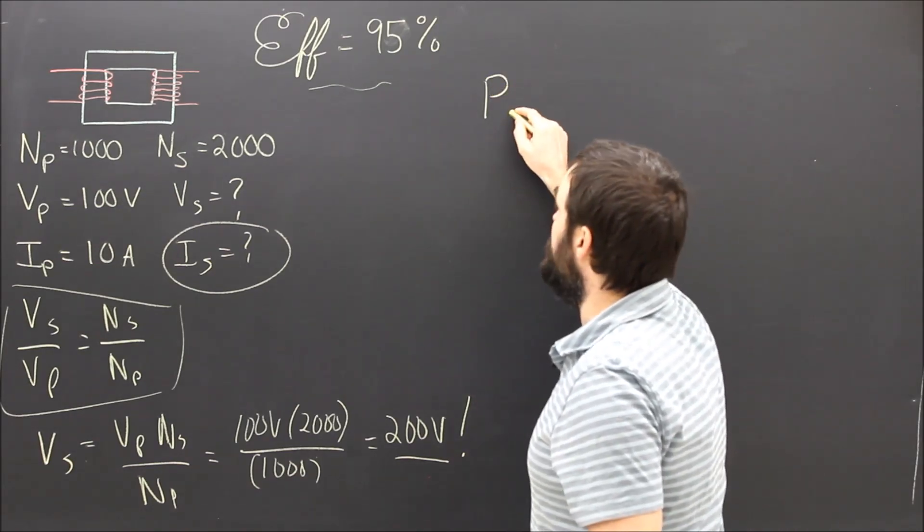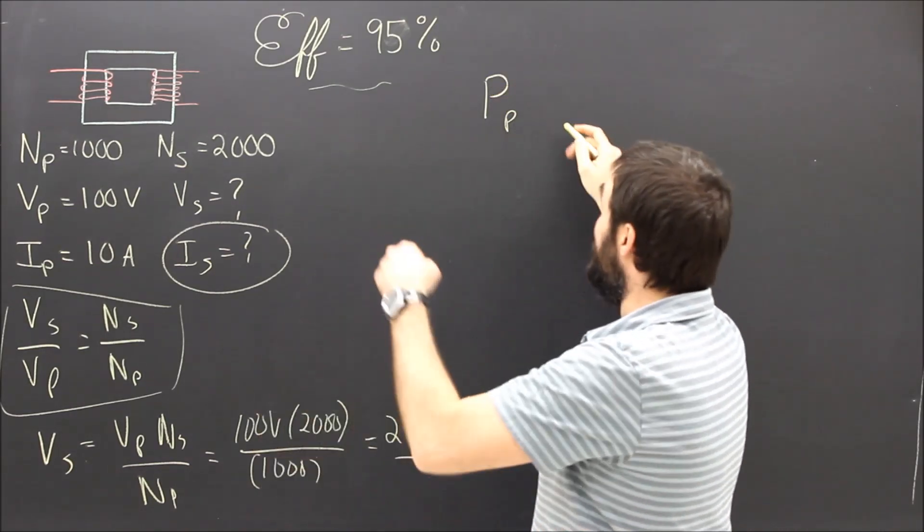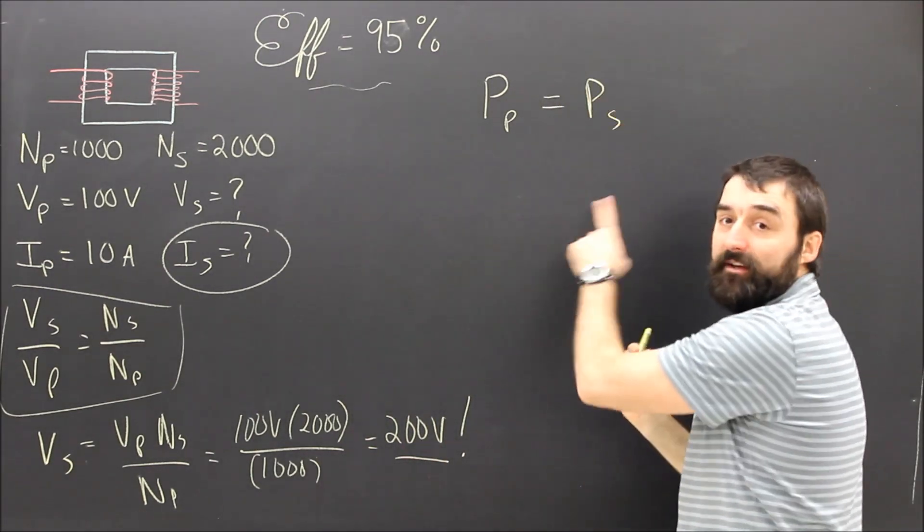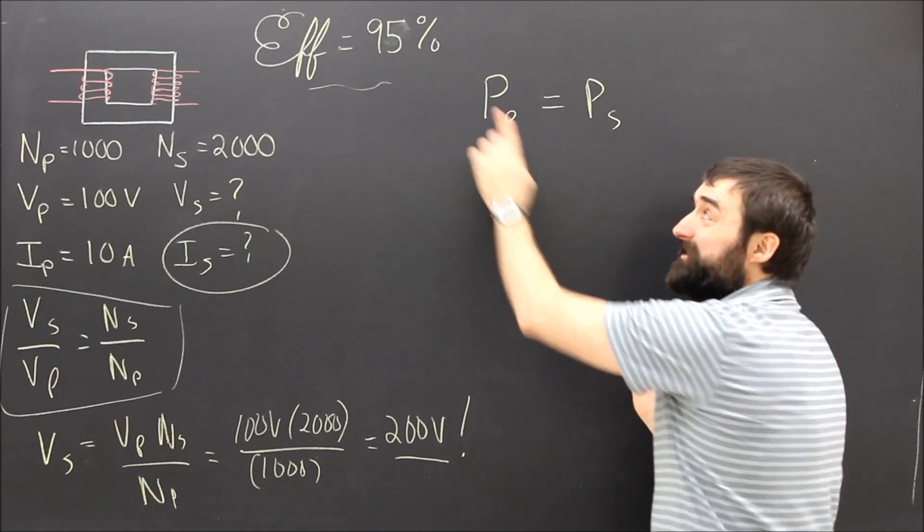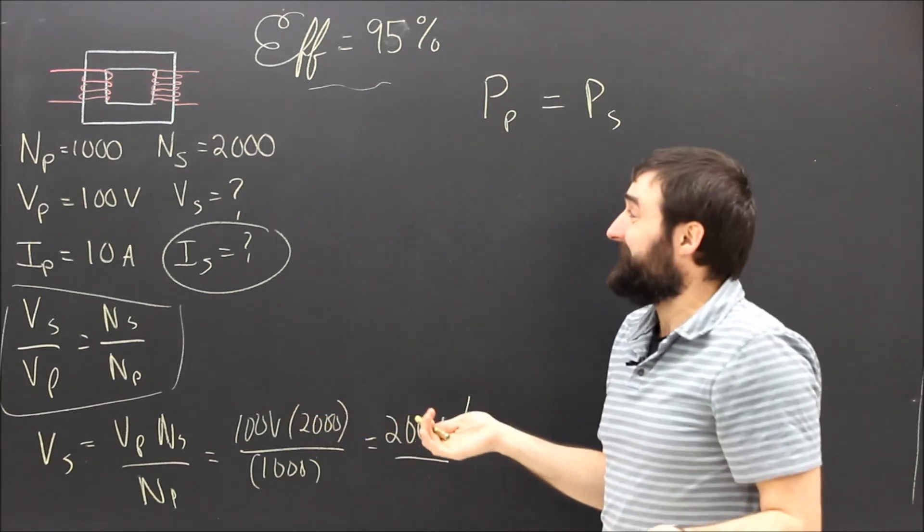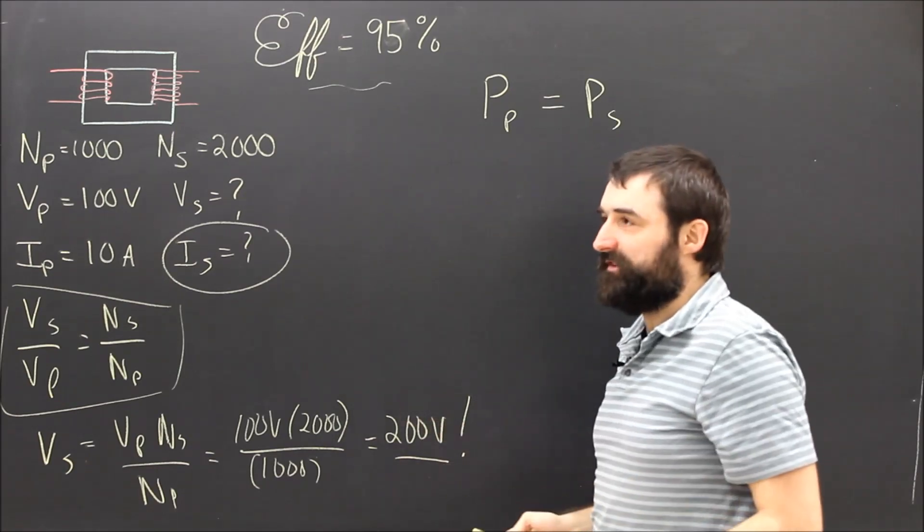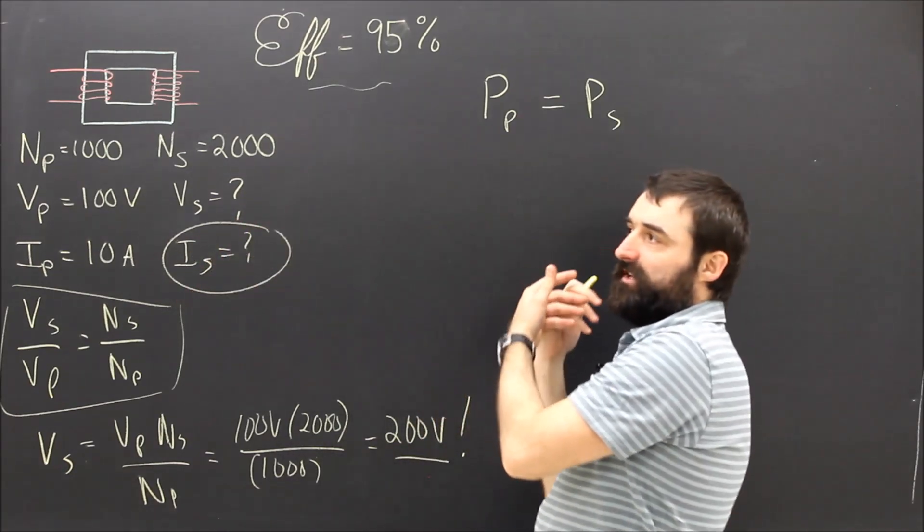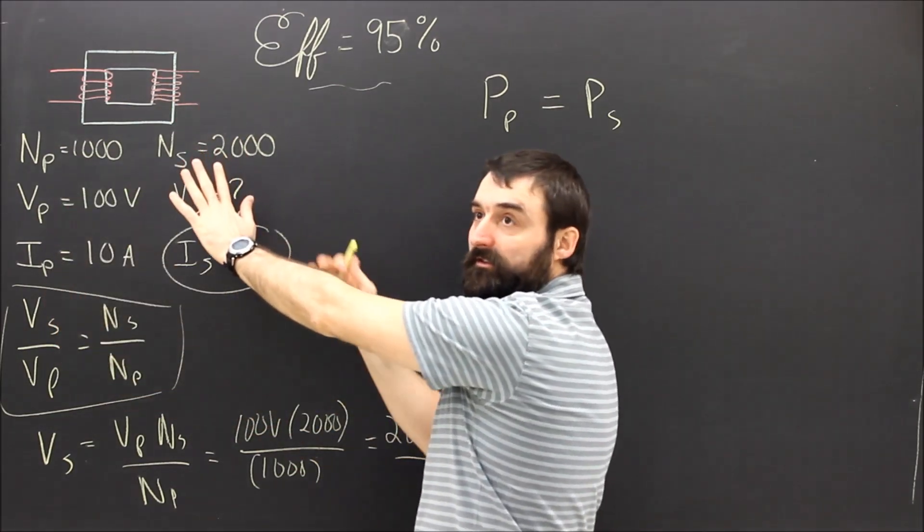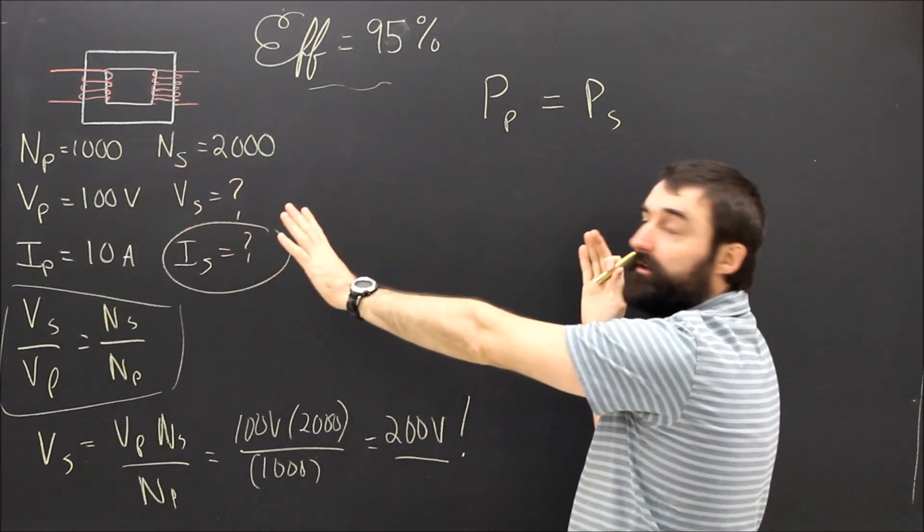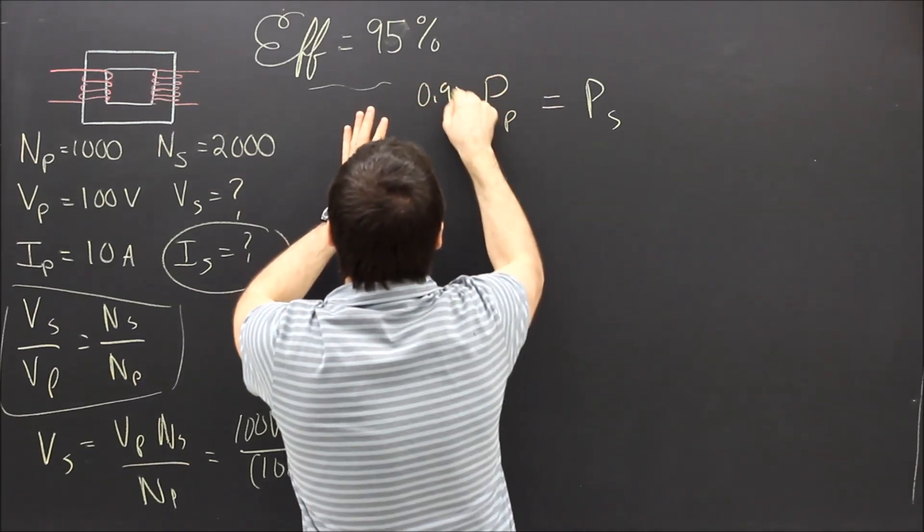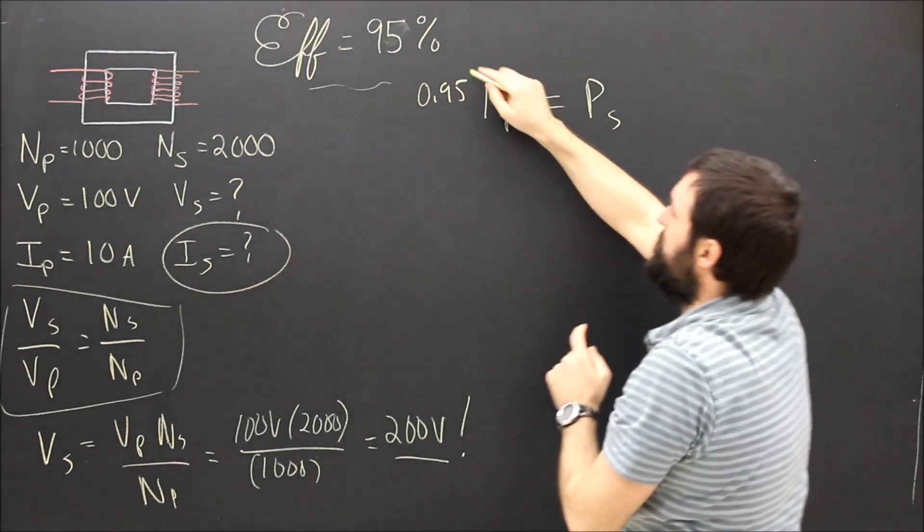If it was 100% efficient, then the power going into the primary would be equal to the power going out of the secondary. That's true if it's 100% efficient, but not anymore. So what do we do? How do we calculate it? If it's only 95% efficient, that means 95% of what goes in comes out. So if we put in 1,000 watts, only 950 are going to come out. So the power that goes in times 0.95 equals the power that goes out.